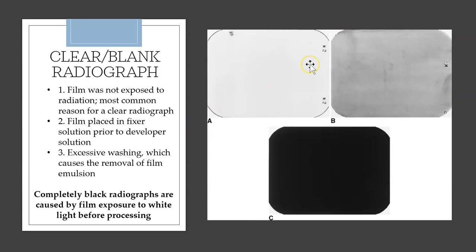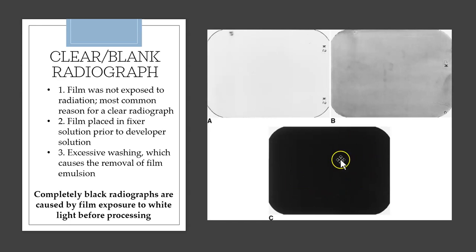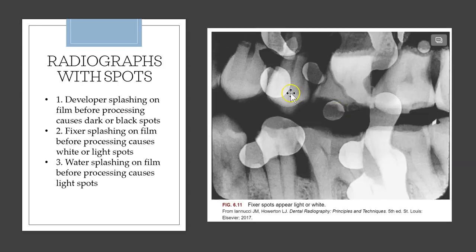A clear radiograph happens when the film was not exposed to radiation — for example, if you didn't push the x-ray button or the film wasn't in the mouth during exposure. A completely black radiograph occurs when the film was accidentally exposed to light and then processed. Radiographs with light dots are caused by fixer spots — fixer solution that splashed on the film before processing.